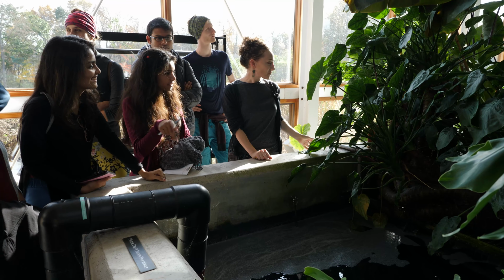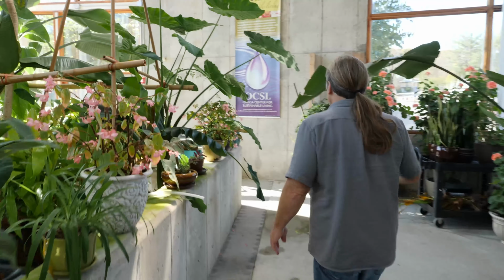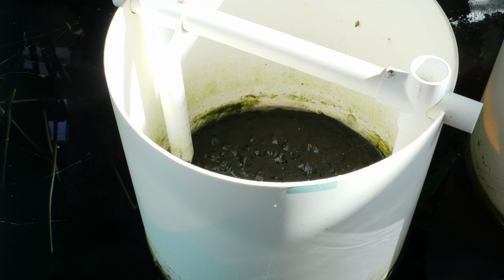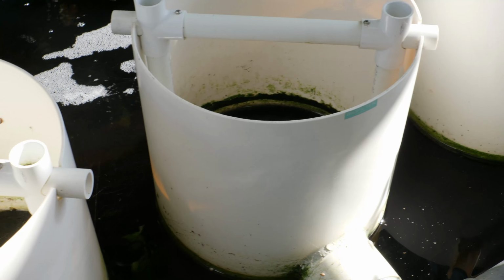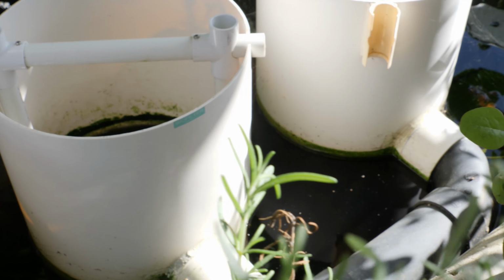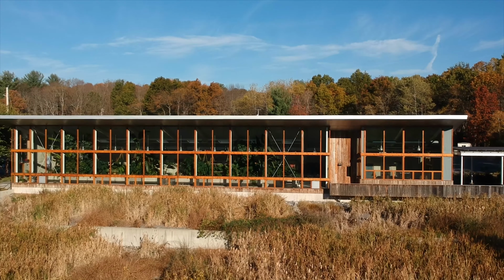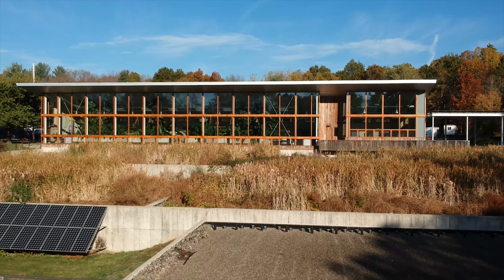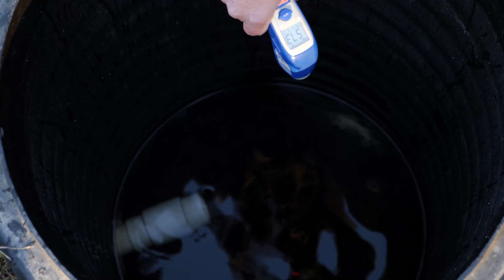So, this water is all flowing? Yep. So this water flows that way. If you take a walk around, you'll see it going that way. Once it goes through all the cells in the lagoon, it's gravity fed down. There's a sand filter at the end, a recirculating sand filter that's, I think, 6.5 feet deep. And that is the final particulates, and once the water comes out of there, the water is clean.